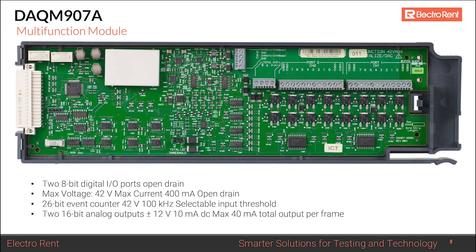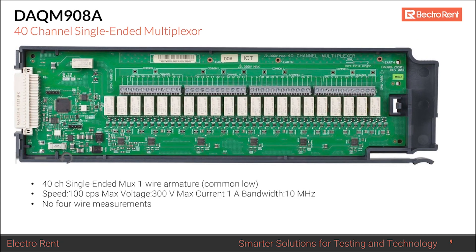The DAQM907A is the multi-function module, similar to the legacy 34907A. It features two 8-bit digital ports for input and output at up to 42 volts, useful for measuring sensor and actuator status. It also includes a 26-bit event counter with 42-volt input and approximately 100 kHz bandwidth, plus two analog outputs at plus and minus 12 volts and a current output of 40 milliamps — capable of driving 4–20 mA current outputs.